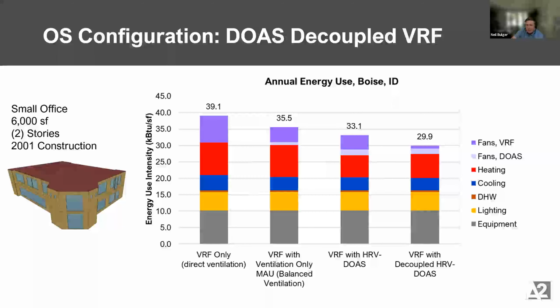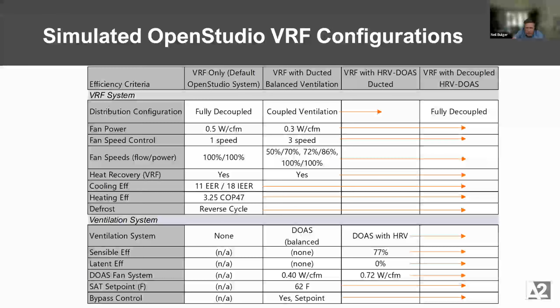So through this, some of the summary inputs of what we did. So just kind of to recap there. We started with a VRF only system. And it has a little bit more fan power, 0.5 watts per CFM. It's very hard to pick a number that is average. You might find many, the ones that are not ducted, very low. Ones that are ducted might be this or higher. But that's what we were looking at. That's the numbers we saw.